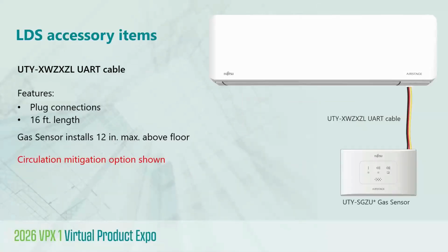So to recap, the first level of mitigation for charge compliance is circulation. Of course, it has to be detected first, but the control action, you might say, is circulation. So to achieve an immediate system shutdown for the system and provide that indoor unit fan override, the two components that you need are what you see there, the gas sensor and the connection cable. So the cable itself is a simple plug and play at both ends, but if the total distance between the indoor unit and gas sensor exceeds 16 feet of wiring length, an expansion kit is going to be required, which we'll get to momentarily. So keep in mind that 16-foot limit.